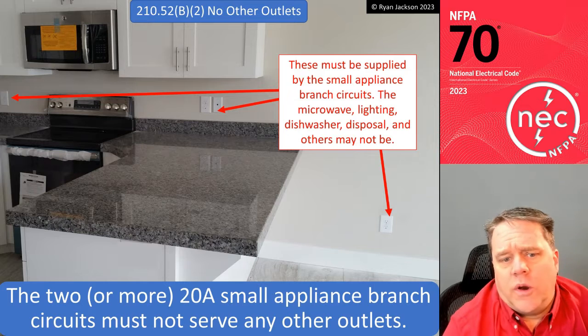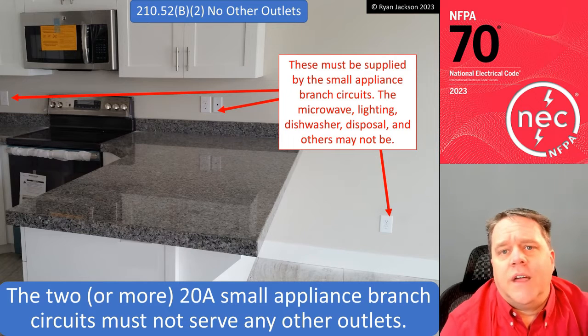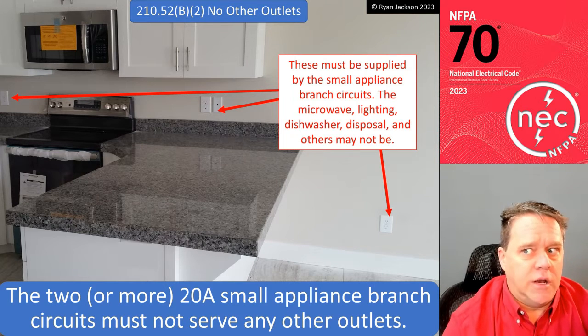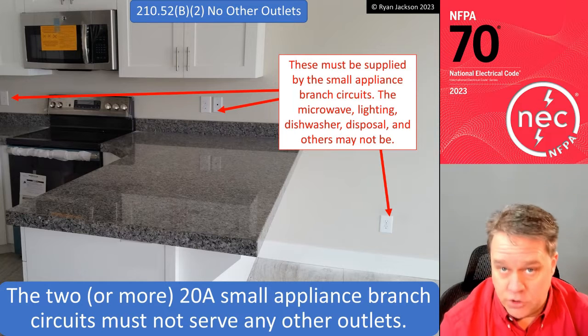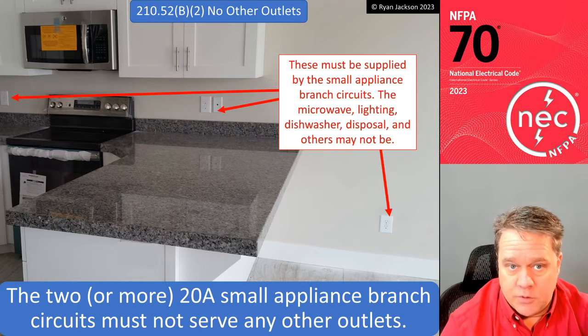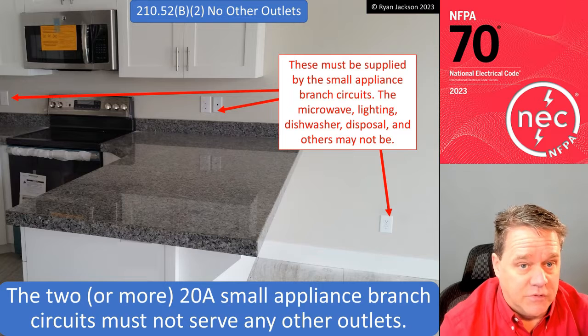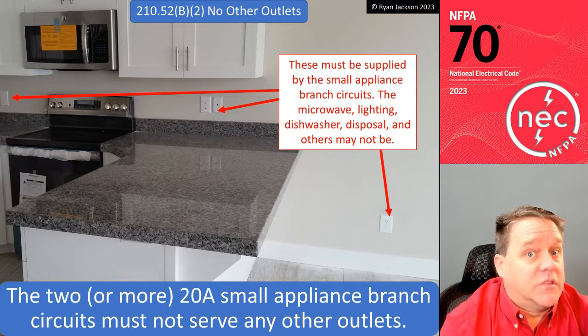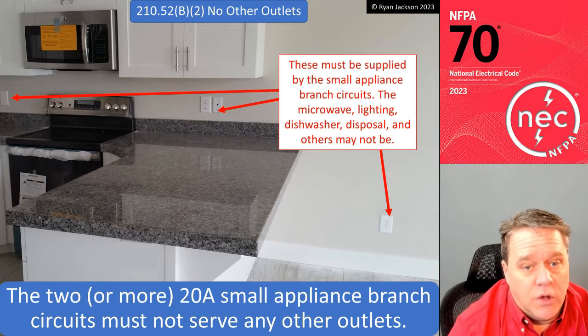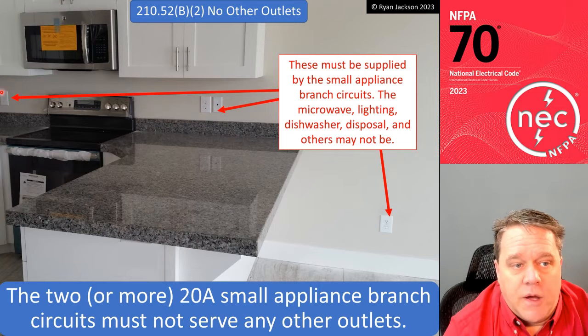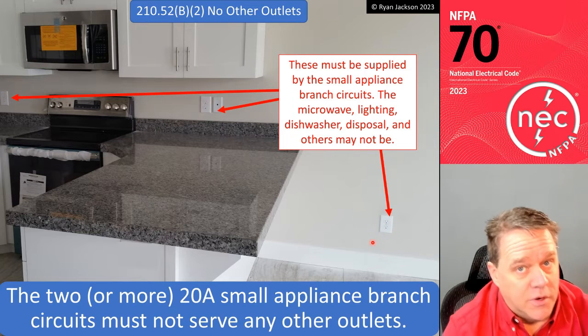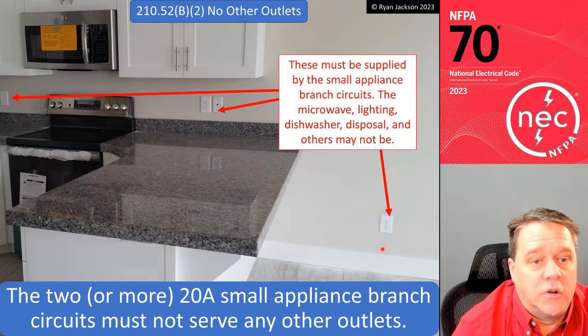The 2 or more 20 amp small appliance branch circuits must not serve any other outlets. Okay, any outlets other than what? Well, the refrigerator, the countertop receptacles, and the wall space receptacles, right? Now, remember, this applies to the dining room too. So looking at this picture, I've got my small appliance branch circuits to hit the countertop and then go into the dining room, right? The dining room has to be on the small appliance branch circuit as well.